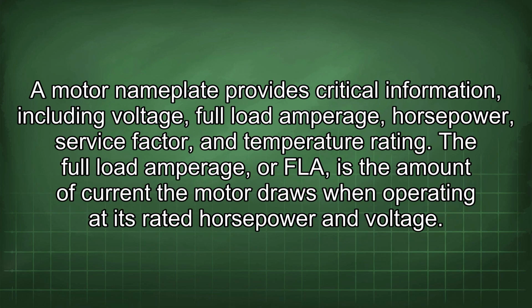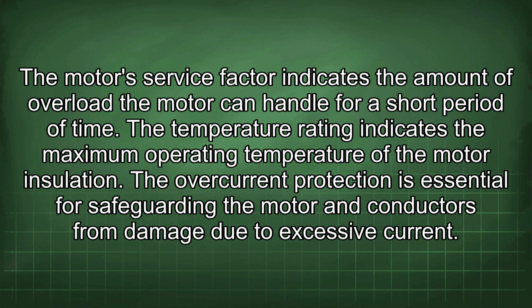A motor nameplate provides critical information, including voltage, full load amperage, horsepower, service factor, and temperature rating. The full load amperage, or FLA, is the amount of current the motor draws when operating at its rated horsepower and voltage. The motor's service factor indicates the amount of overload the motor can handle for a short period of time. The temperature rating indicates the maximum operating temperature of the motor insulation.